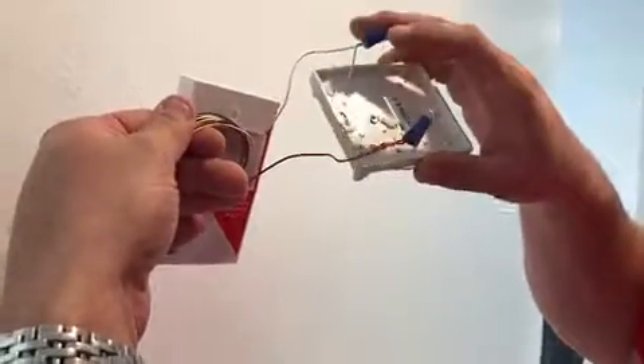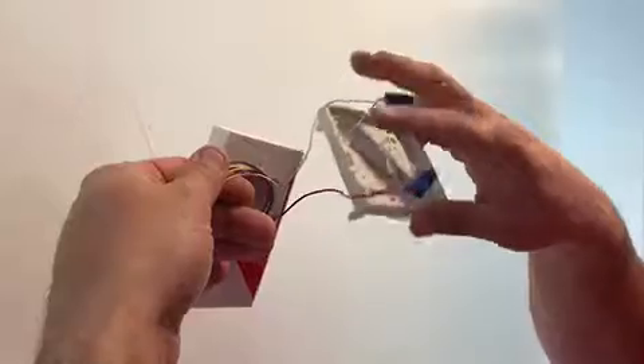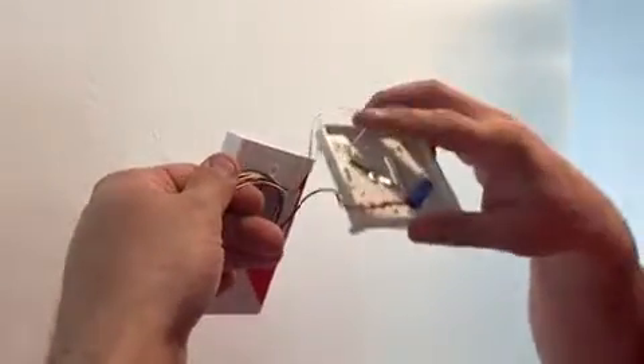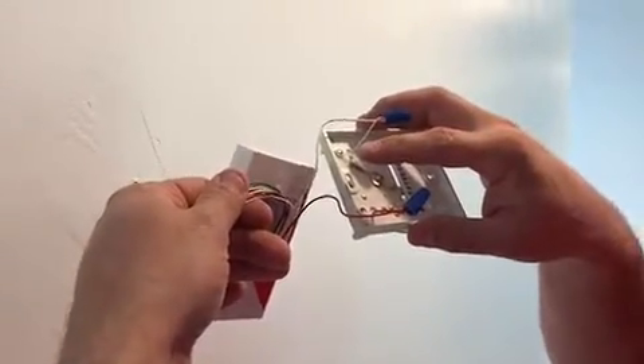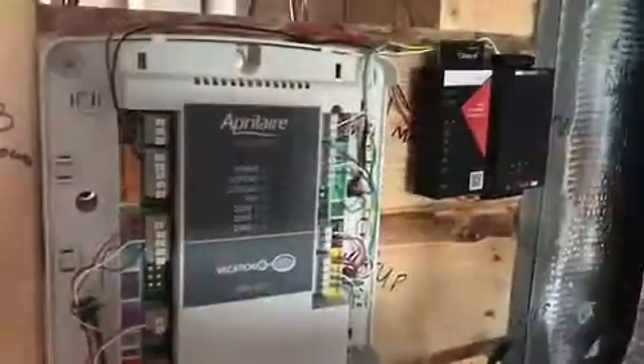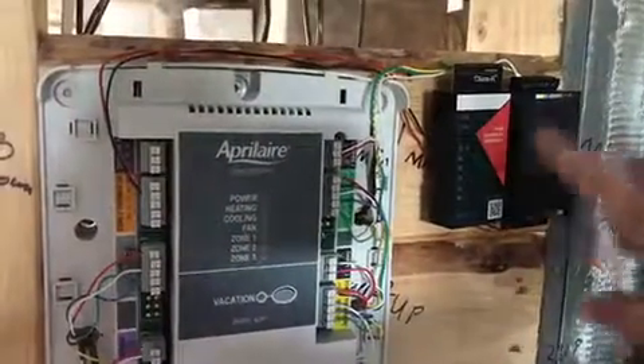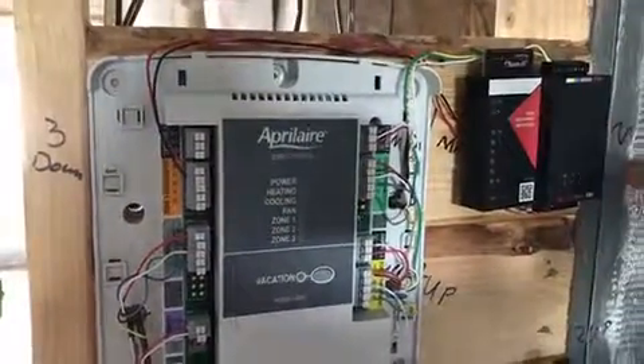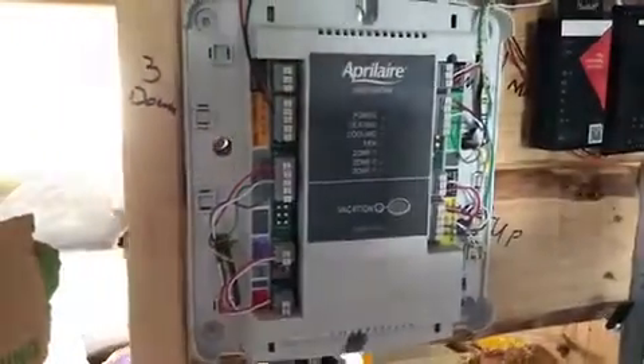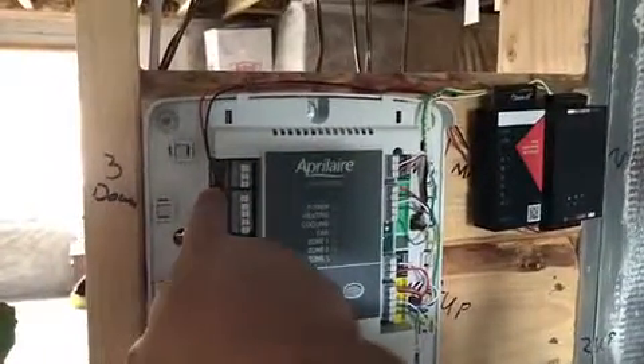I'm going to find the wires that we need to connect into the thermostat. In this case, I've so far got the white and the red connected, and then we'll connect the rest of the control wires, and then we'll go downstairs. Okay, so here you can see we've got the HVAC equipment interface mounted here to the board. We've got the R and common. We had an R and common here. We could just take power off of there, connect it to the left side down here.